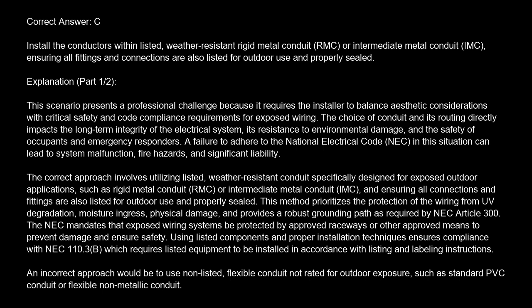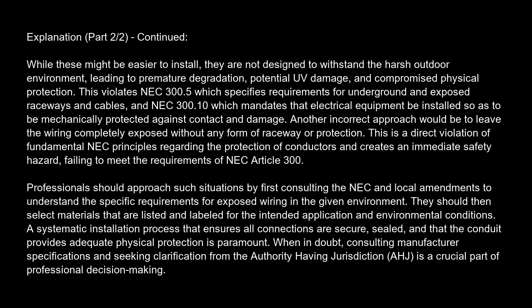An incorrect approach would be to use non-listed, flexible conduit not rated for outdoor exposure, such as standard PVC conduit or flexible non-metallic conduit. While these might be easier to install, they are not designed to withstand the harsh outdoor environment, leading to premature degradation, potential UV damage, and compromised physical protection. This violates NEC 300.5, which specifies requirements for underground and exposed raceways and cables, and NEC 300.10, which mandates that electrical equipment be installed so as to be mechanically protected against contact and damage. Another incorrect approach would be to leave the wiring completely exposed without any form of raceway or protection. This is a direct violation of fundamental NEC principles regarding the protection of conductors and creates an immediate safety hazard, failing to meet the requirements of NEC Article 300.